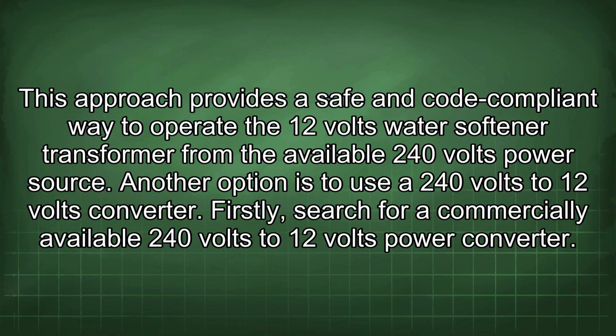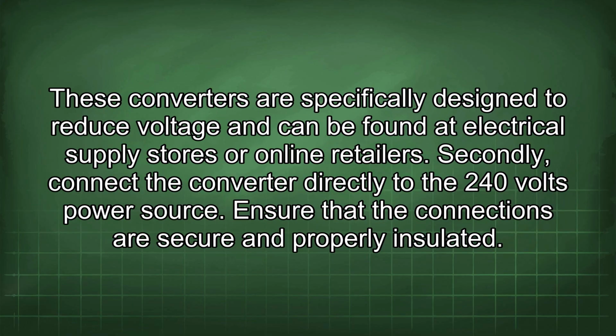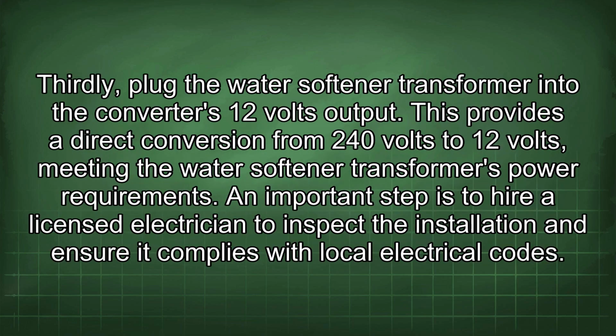This approach provides a safe and code-compliant way to operate the 12 volts water softener transformer from the available 240 volts power source. Another option is to use a 240 volts to 12 volts converter. Firstly, search for a commercially available 240 volts to 12 volts power converter. These converters are specifically designed to reduce voltage and can be found at electrical supply stores or online retailers. Secondly, connect the converter directly to the 240 volts power source. Ensure that the connections are secure and properly insulated. Thirdly, plug the water softener transformer into the converter's 12 volts output. This provides a direct conversion from 240 volts to 12 volts, meeting the water softener transformer's power requirements.